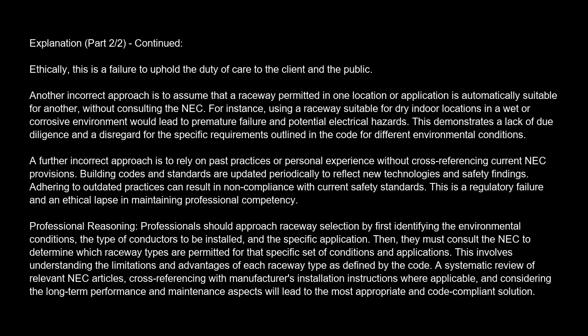Another incorrect approach is to assume that a raceway permitted in one location or application is automatically suitable for another, without consulting the NEC. For instance, using a raceway suitable for dry indoor locations in a wet or corrosive environment would lead to premature failure and potential electrical hazards.